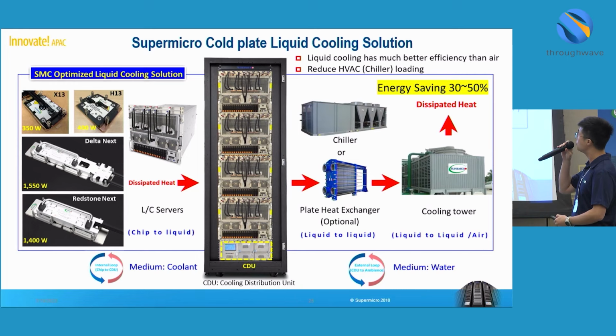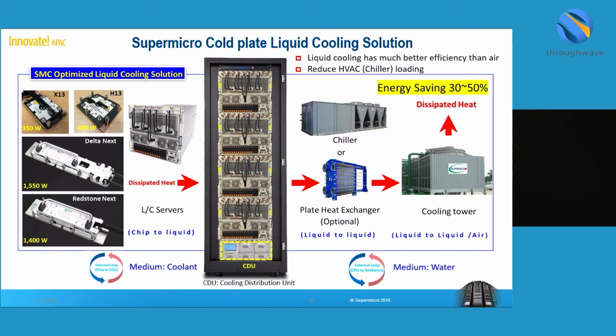So this is Supermicro's cold plate liquid cooling solution. The heat dissipation goes from left to right. The heat is dissipated from the server to the CDU, which is the coolant distribution unit in the rack, and then to the chiller, and finally the heat is dissipated outside by the cooling tower.